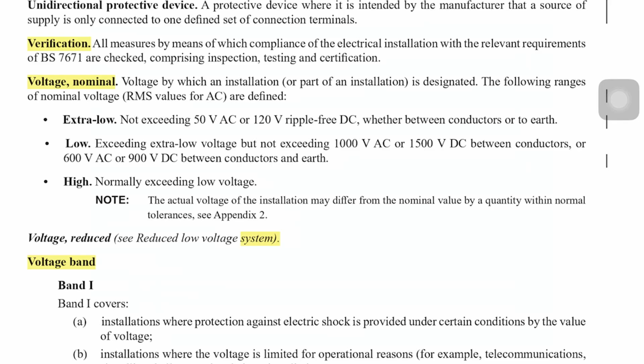Extra low voltage here is not exceeding 50 volts AC or 120 volts ripple-free DC, whether between conductors or to earth. The bit you need to be familiar with, and I think this is where everybody's rammed home about it, is that 7671 covers voltages right up to 1000 volts AC and 1500 volts DC. But what's not fully appreciated is the text that's here: low voltage exceeds extra low voltage, but not exceeding 1000 volts AC or 1500 volts DC between conductors - that's live conductors, L and N, L1 and L2, L1 and L3, etc.